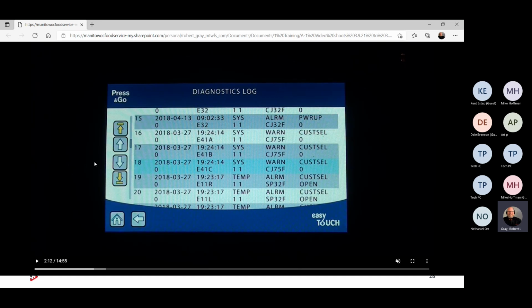But that's going to indicate that phase A, or phase 1, or phase X, if you're using X, Y, and Z, is bad in the contactor, something going on inside that contactor. Replace the contactor. Okay. If it's a single A and you have the voltages coming into the contactor and out of the contactor as you should, you're going to check your connections, and you're also going to go down to your solid state relay board to check the wiring there as well. Check again, the black and the red are for the phases, phase 1, phase 2. You check across that. Whatever you had on the output, you should have on the input of the solid state relay board. So you're going to check your connections.